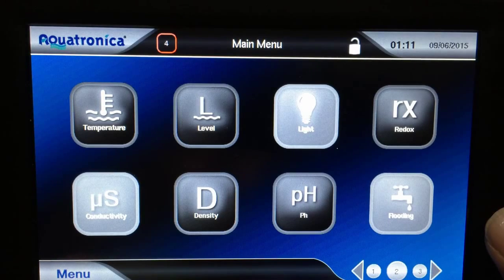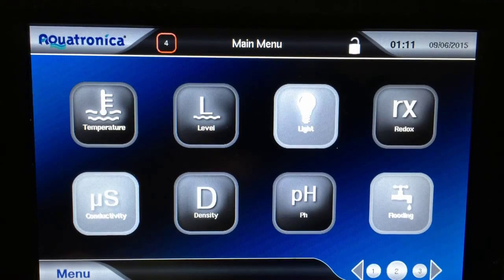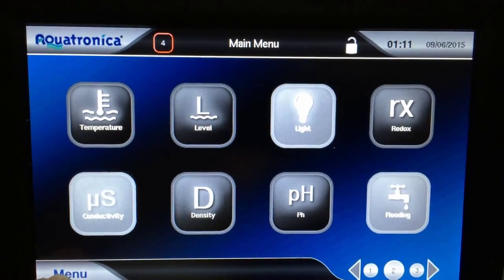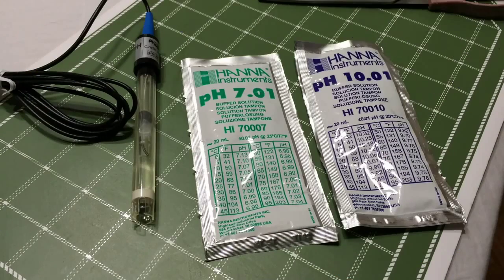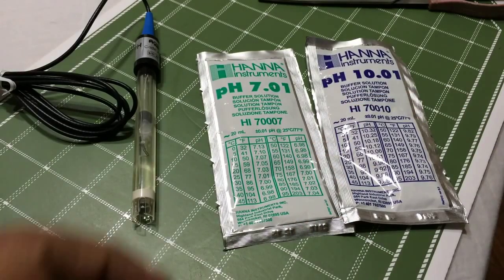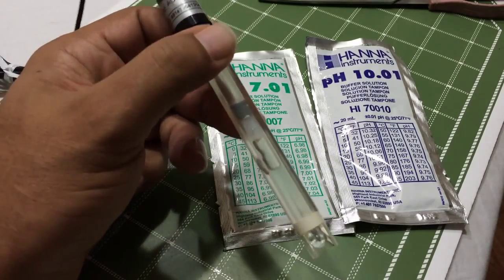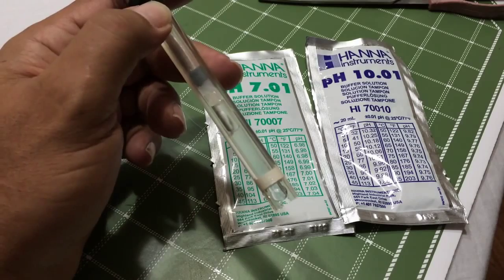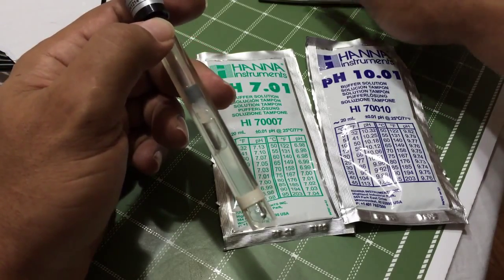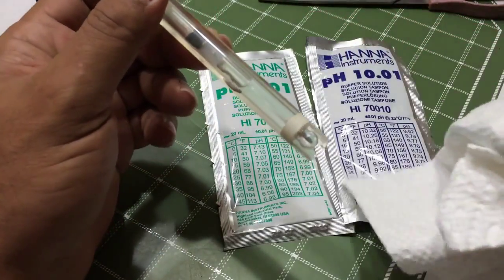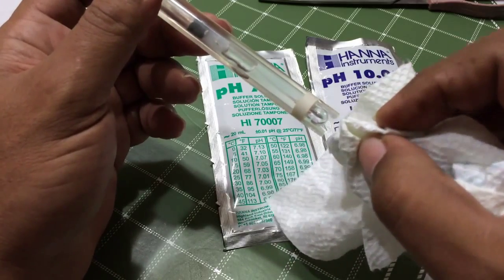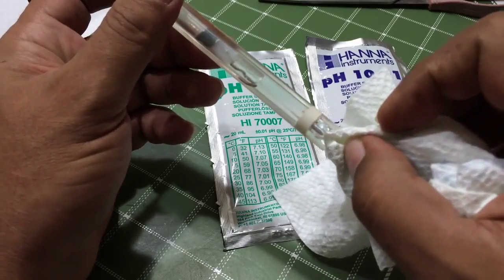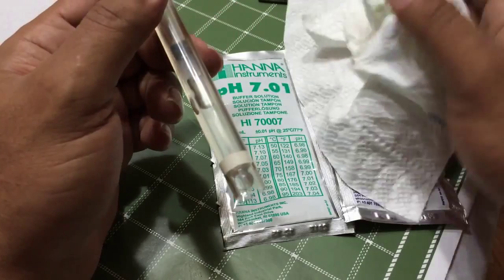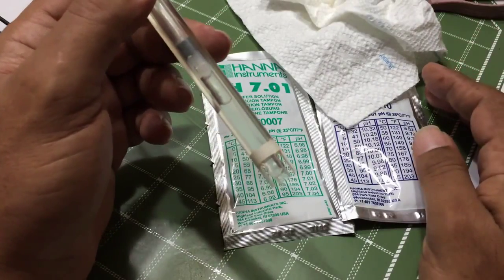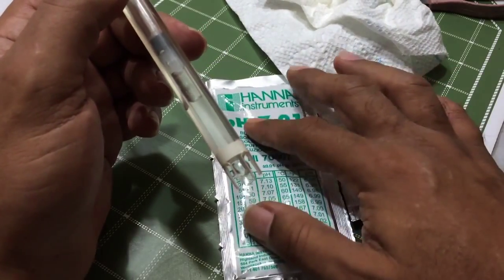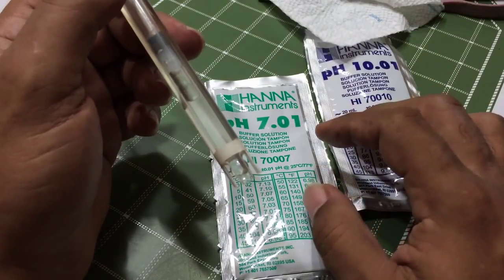So to do that, first you're going to need to have your pH probe and thing ready. So I'm going to move over the camera a bit here and show you what you need to have. Okay, for a new pH probe, or any new probe, you don't have to go through a whole bunch of cleaning. All you normally need to do is just rinse it off with RO water and have a paper towel, dry off the body, try to just dab a little bit around the edges here. You want to just get out as much water as you can. Don't go too far in. You just want to basically get off as much of the water as you can that might be left over from the RO, because it'll dilute the sample and the reference samples you're using if you don't do that.